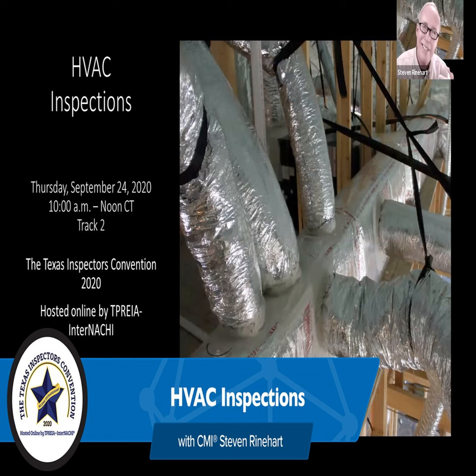Rarely do you see that somebody hasn't been in there splicing, changing wires. But if you see something wrong in there, it's really a problem. More likely than not, if you're not getting 20, 30 degrees of heat in an electric furnace, when it's run for a little while and everything's warmed up, you're probably not getting all those strips.